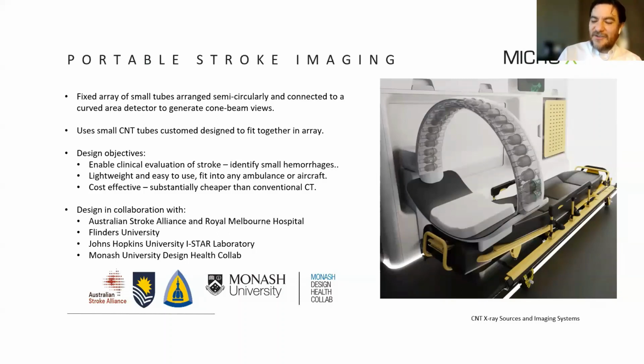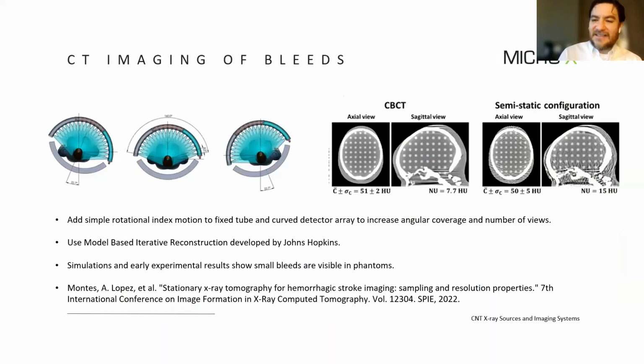And as you might imagine right away, people are thinking, well, how do you get full image quality out of this array? And so what we've done is, rather than have it be a completely static system, the system itself tilts slightly. And by tilting, it takes all of the views and then indexes the whole system, and then takes another static array. And by doing that, we're actually able to get a full cone beam CT reconstruction of the brain. It's a sparse view CT reconstruction. The first work was done looking at model-based iterative reconstruction, and we were able to show in simulation that we could see very small bleeds.